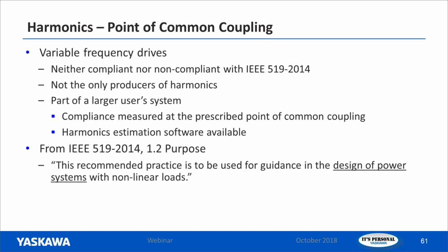Variable frequency drives are neither compliant nor non-compliant with IEEE 519. And also, they're not the only producers of harmonics. A VFD is a nonlinear load, but really anything converting AC to DC is a nonlinear load. Copy machines in the office, printers, your computers, those are all nonlinear loads. It's part of a larger user's system, so compliance needs to be measured at the point of common coupling. And harmonics estimation software is available for doing that. I mean, if you know the VFDs that are going to be hanging off of a transformer, you can run a harmonic calculation with free software. Most of the major VFD manufacturers do provide that software free on their website, and I know Yaskawa does as well.